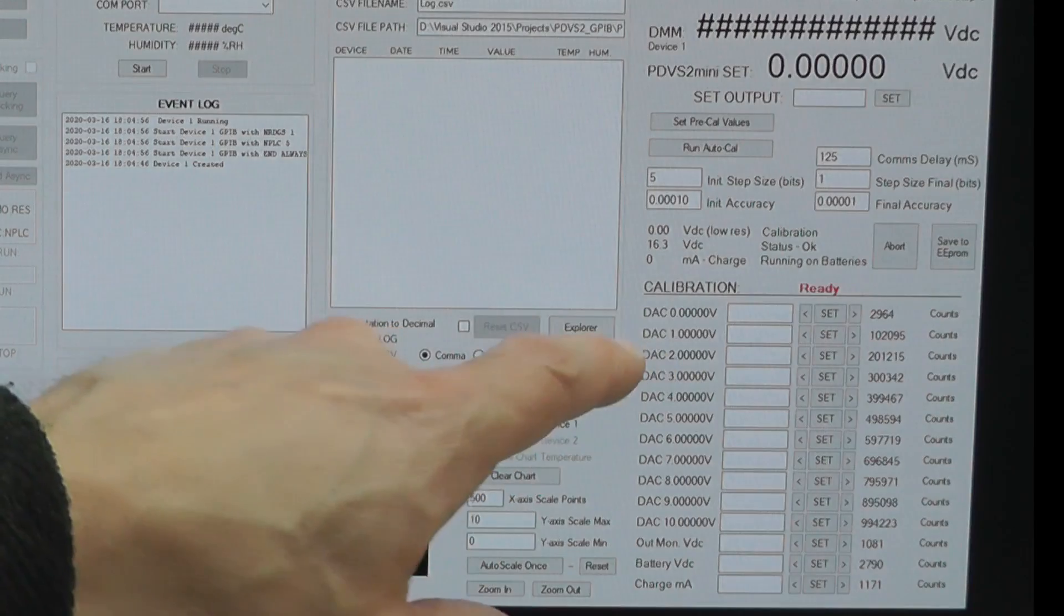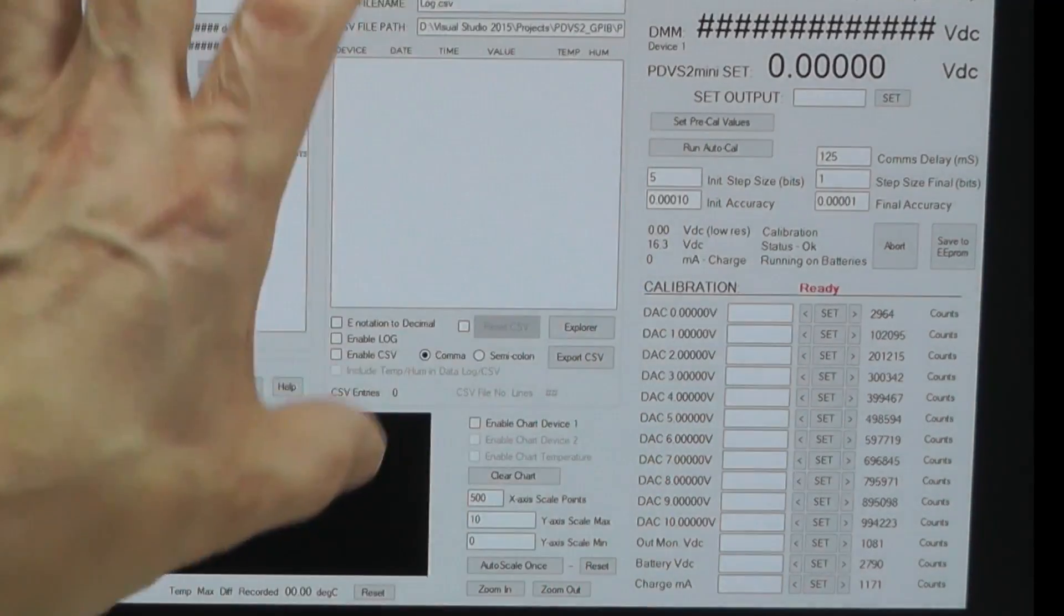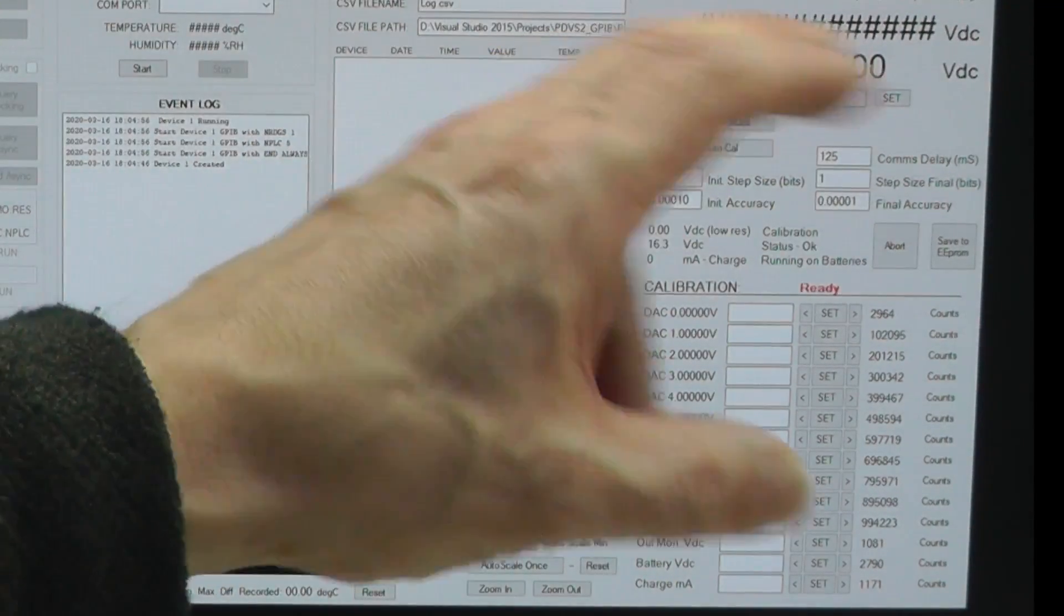And then what will happen is based on the value for instance DAC 0 volts here - that's the first set point - a value will be loaded in there and then the program will either step up or step down depending on which direction it detects it needs to go in, in order to achieve 0 volts from the 3458A. Because this is what the program will set out first is the zero volts here and then once zero volts is done the program will then instruct the PDV-S2 mini to output one volt and then the program will be looking for exactly one volt from the 3458A, again stepping up or stepping down until it achieves that value. There's other things like a comms delay and a step size and that sort of thing there...